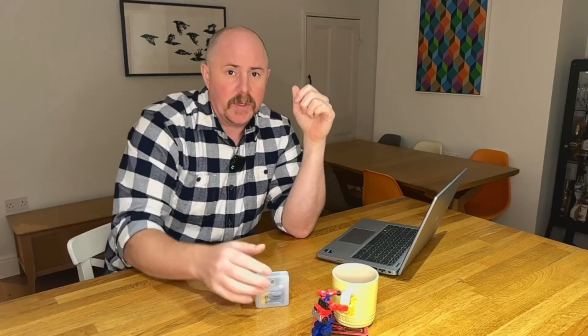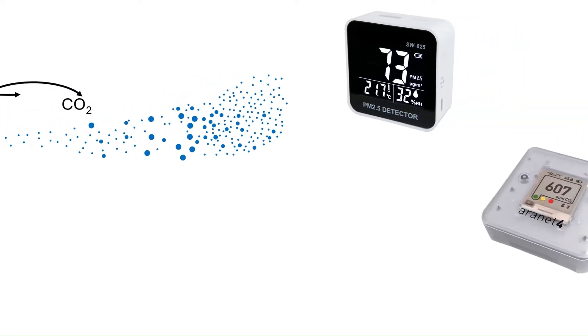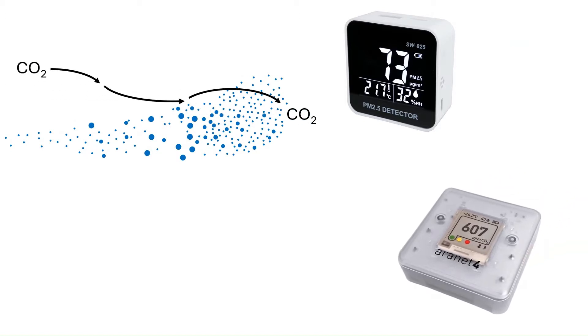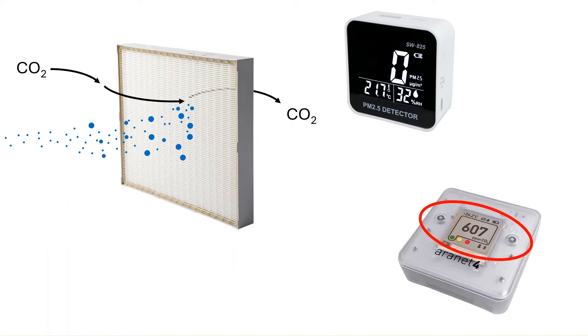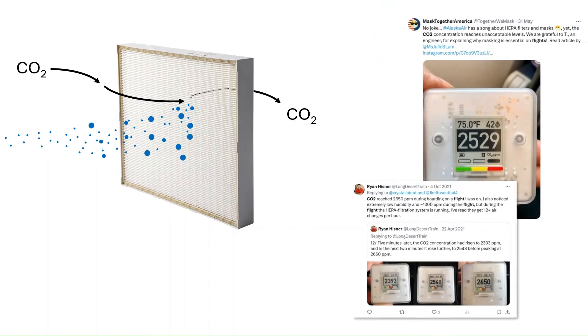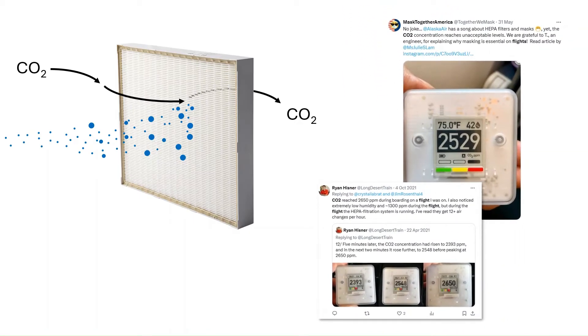Given that SARS-CoV-2 is airborne, one way we can limit transmission is through ventilation — basically physically removing the aerosol from the space. CO2 monitors are outstanding at helping us understand ventilation, with the assumption that both infectious aerosol and CO2 originate from the same source. There are two ways airborne viruses are physically removed: filtration passes air through a filter, which effectively removes the aerosol but does nothing to change CO2 concentration. So when filtration is used, the perceived risk indicated by CO2 may be much higher than the actual risk. For example, people commonly report high CO2 on airplanes, but since the air is heavily filtered, the amount of infectious aerosol will be far lower than the CO2 monitor suggests.